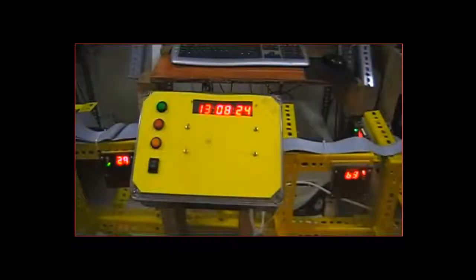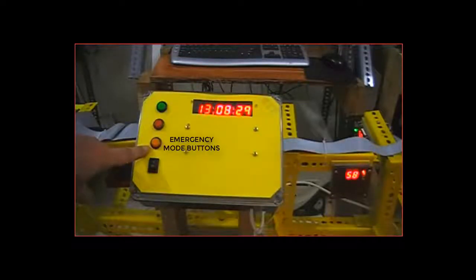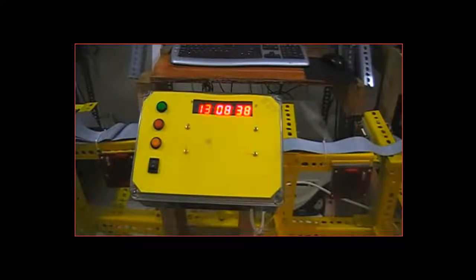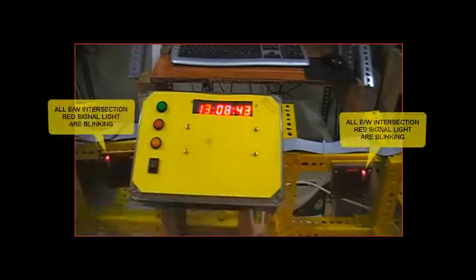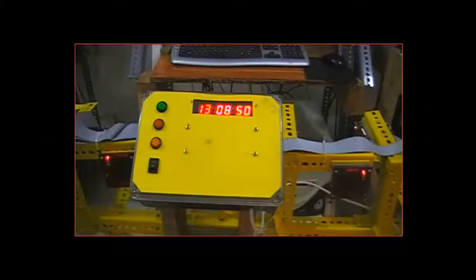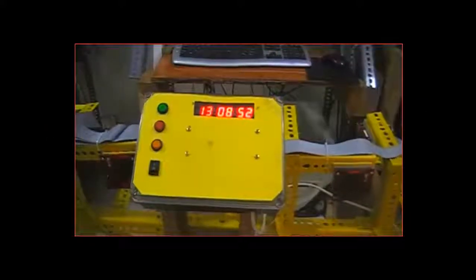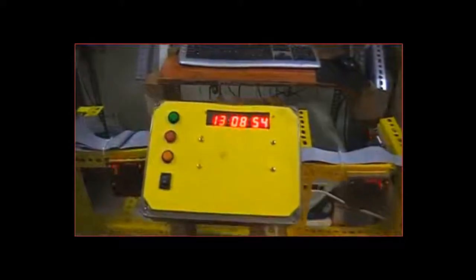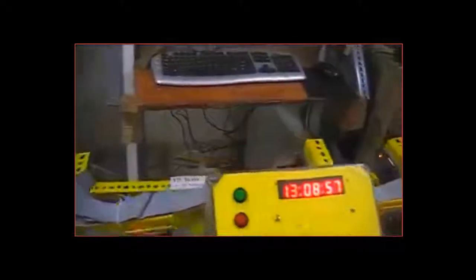As I mentioned already, by this emergency push button, when you depress it, it goes to emergency mode. Right now, notice that all east-west streets are showing the signal lights turned to blinking red, and at the same time, all the north-south intersection signal lights change to yellow.